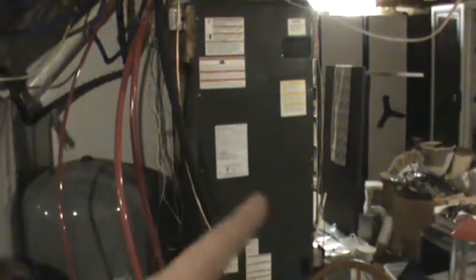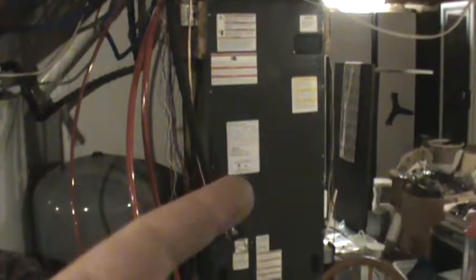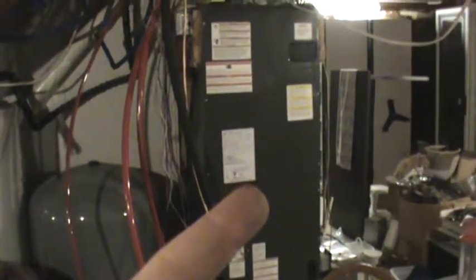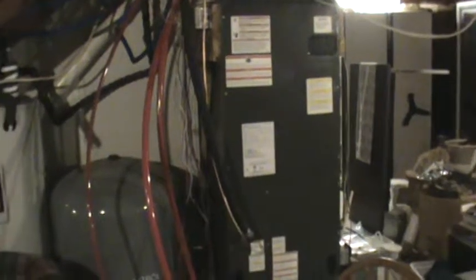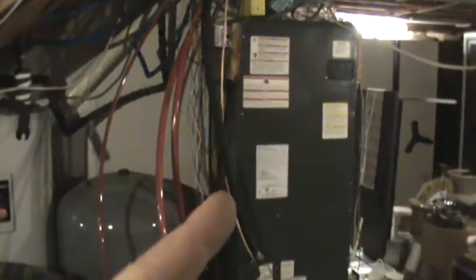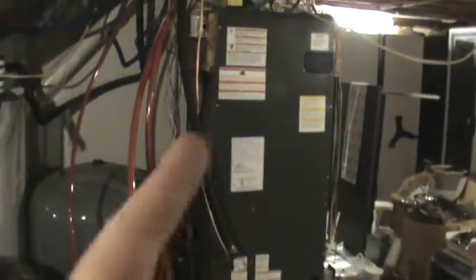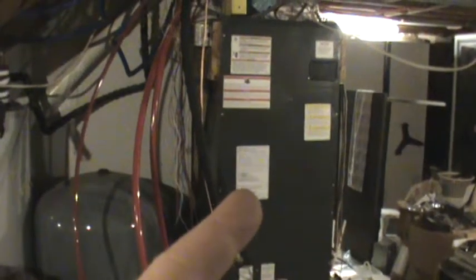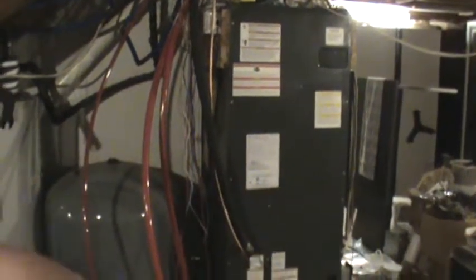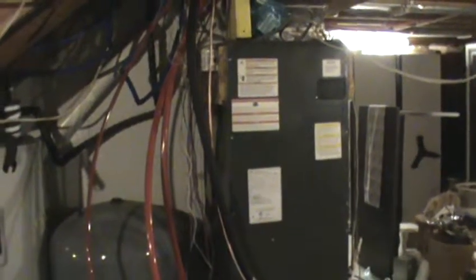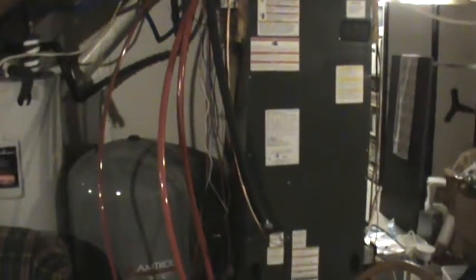It goes through the A coil first, so that the A coil can remove heat from it. And actually, the only thing that can come out of the A coil in cooling or in heating mode is liquid. So you're taking the gas and you're condensing it. So you're removing the latent heat of vaporization from the refrigerant, but the refrigerant is still at a relatively high temperature. So after going through the A coil in here, like I said, there's a thermostatic expansion valve inside of here that then allows the pressure drop to occur, so that some of the refrigerant boils off. Now, yeah, that's right. I got to check myself. So some of the refrigerant then boils off, cooling it down, and goes through this return.